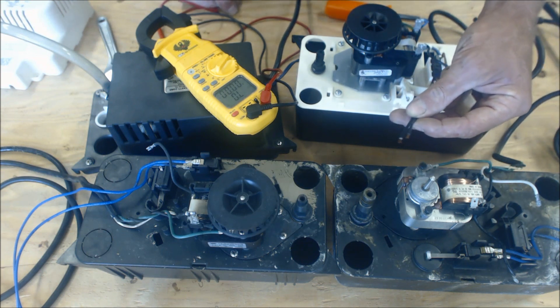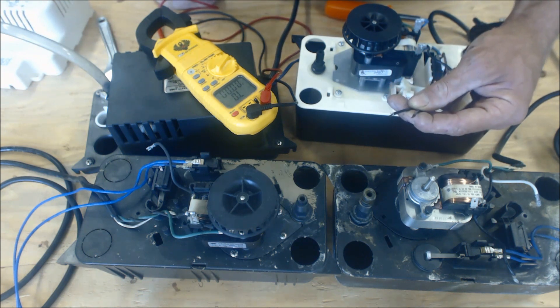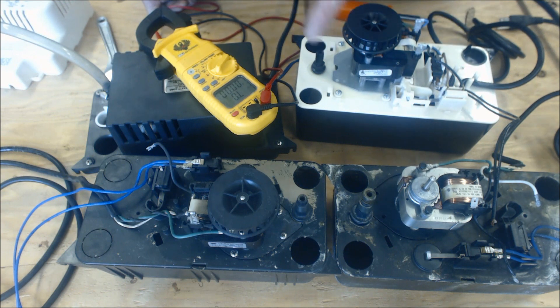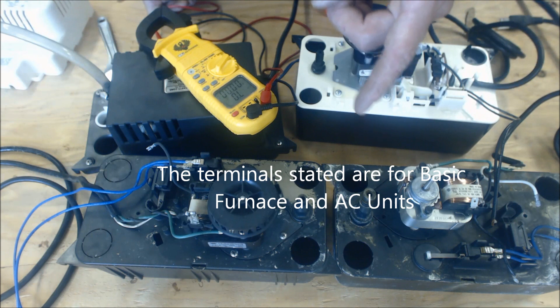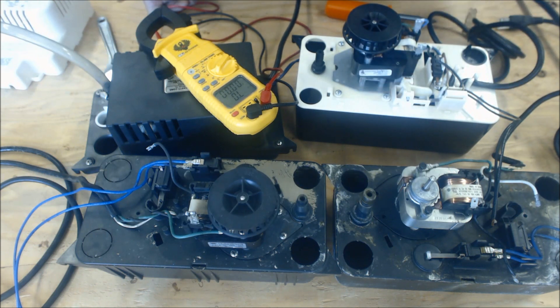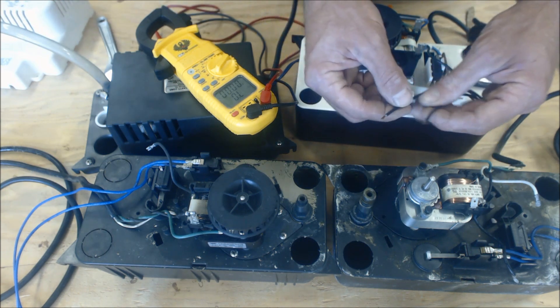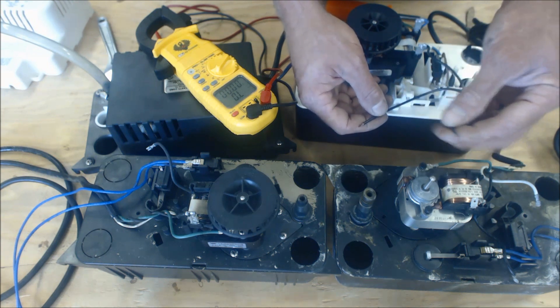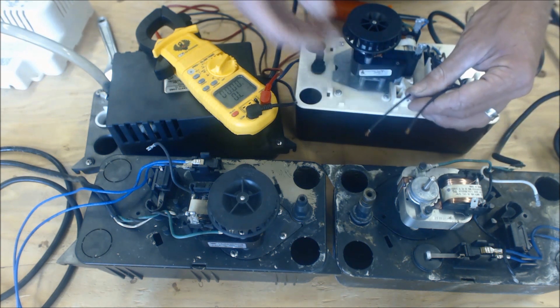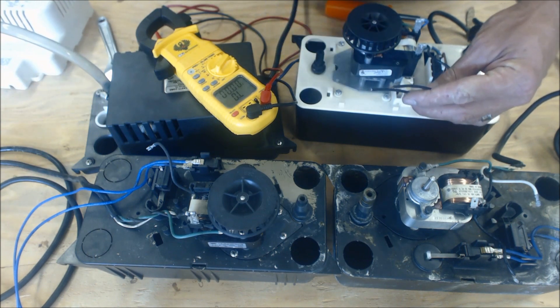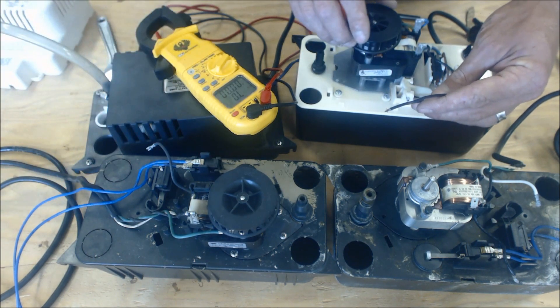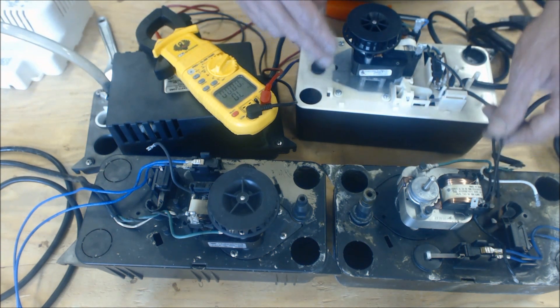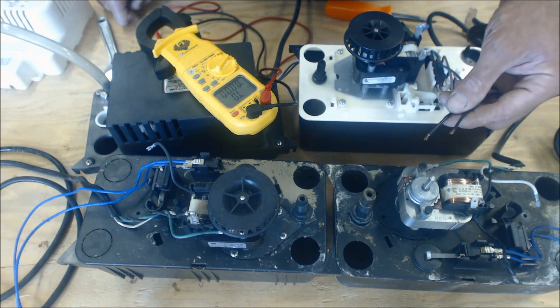So you need to break either the Y wire or the red wire going right to your thermostat. But on your control board, your red comes off your R terminal and that's 24 volts. And it comes back to Y for cooling, W for heat, or G for fan. If you break the wire and you install say this the Y terminal and this to your yellow wire that was going to your Y terminal on your control board, that will not allow the outdoor condenser to run. Which means that condensate would not be gathering in here.